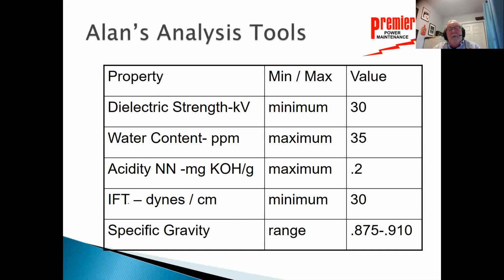Now, I have some analysis tools that I've taken from various groups, the IEEE and SD Myers and those companies. There are some values that stick out. For dielectric strength, we want it to be at least 30 kV minimum. Water content, maximum of 35 parts per million. Now, I want you to understand that a lot of people truly don't look at the water content properly, because water content is a function of temperature.